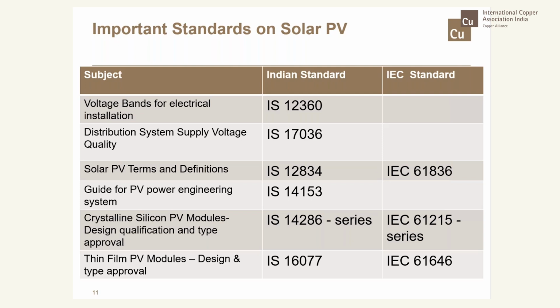The important standards I have kept in the first two cases are the voltage band for electrical installation, which is IS 12360. This is important in the sense that it talks about the standard reference voltages and frequencies, because these are necessary for integration of the various systems that will be connected in the solar PV system. So also distribution power quality, like harmonics. Then solar PV terms and definitions, with corresponding Indian standards and IEC standards. The guide for PV power engineering systems is IS 14153. Then the important PV module standard is the IS 14286 series. The corresponding IEC is the 61215 series. So also PV films, IS 16077, and the IEC standard is 61646.